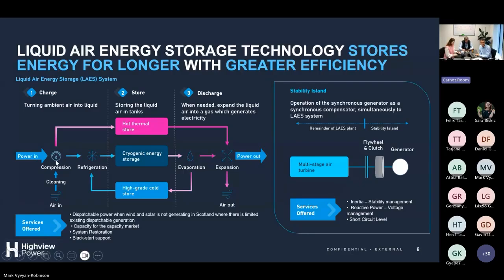On the left hand side is the compressor. We take normal ambient air, clean it, remove the carbon dioxide and moisture, then compress it. The waste heat is stored, and I'll come back to that. We compress it, cool it, and store it in large steel vessels as liquid air, cryogenic air. When we want that energy back, we expand it, putting it through a turbine to generate electricity. During that expansion process, we again store the waste heat.